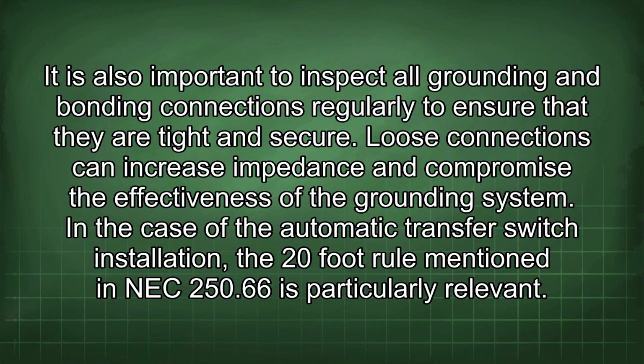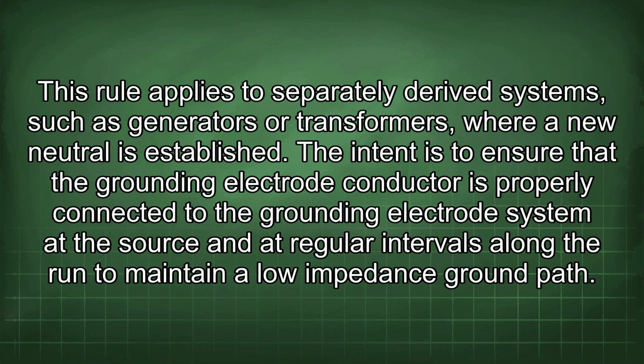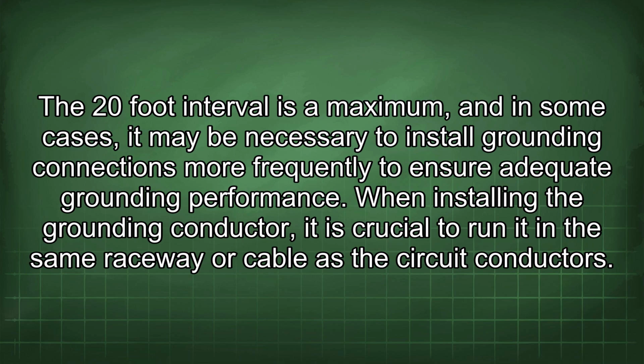In the case of the automatic transfer switch installation, the 20-foot rule mentioned in NEC 250.66 is particularly relevant. This rule applies to separately derived systems such as generators or transformers, where a new neutral is established. The intent is to ensure that the grounding electrode conductor is properly connected to the grounding electrode system at the source and at regular intervals along the run to maintain a low impedance ground path. The 20-foot interval is a maximum, and in some cases, it may be necessary to install grounding connections more frequently to ensure adequate grounding performance.